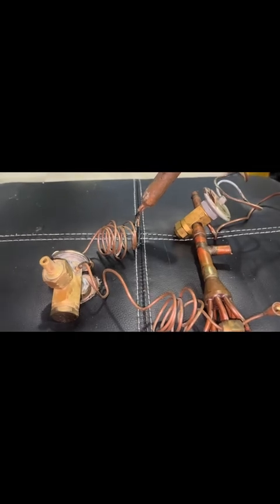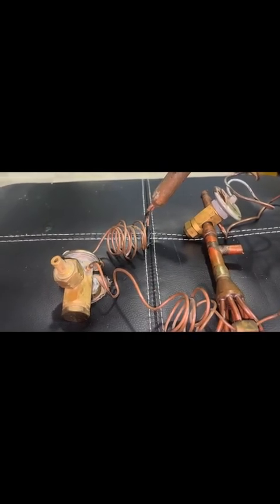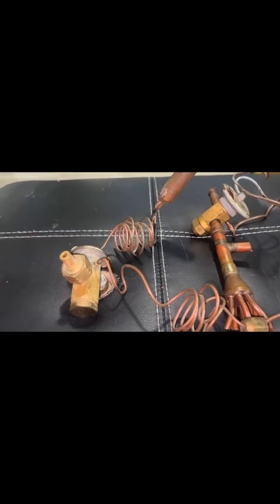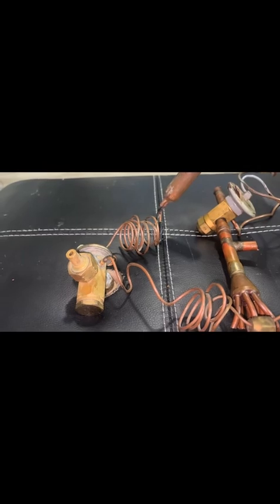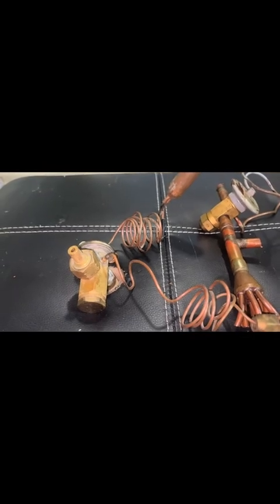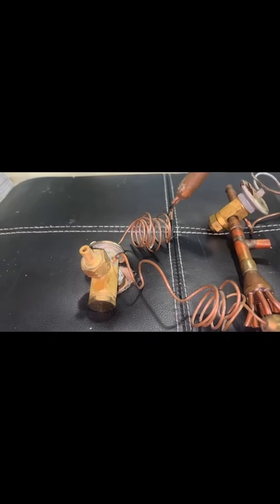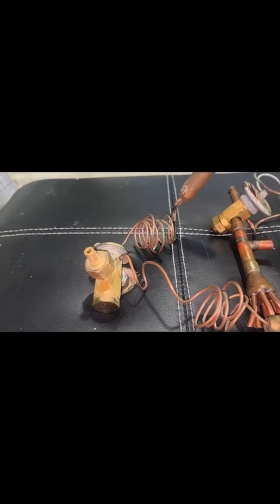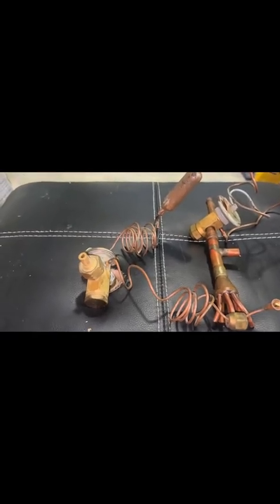The pros would be they're more efficient, at least I believe 15% better than pistons. It adapts to load changes. It prevents liquid slugging, meaning it's more protecting of the compressor. Better cooling. It simplifies charging by using the subcooling method. The cons would be they're more complex, they're more expensive, more components that can fail.